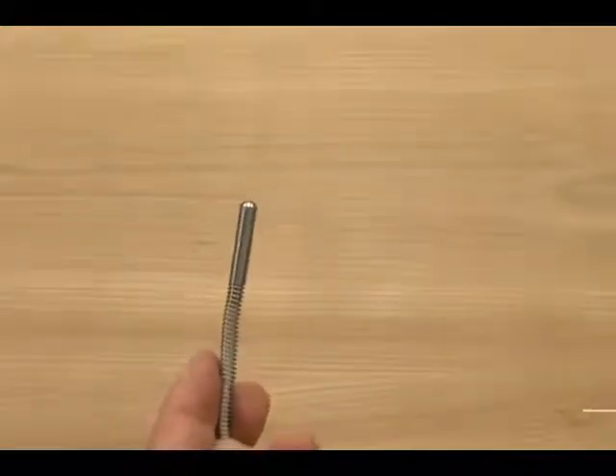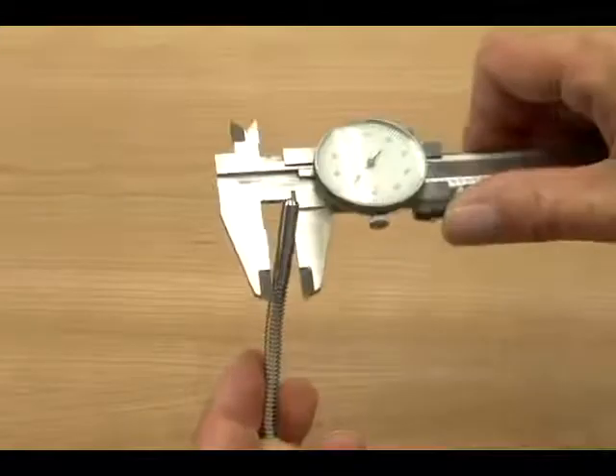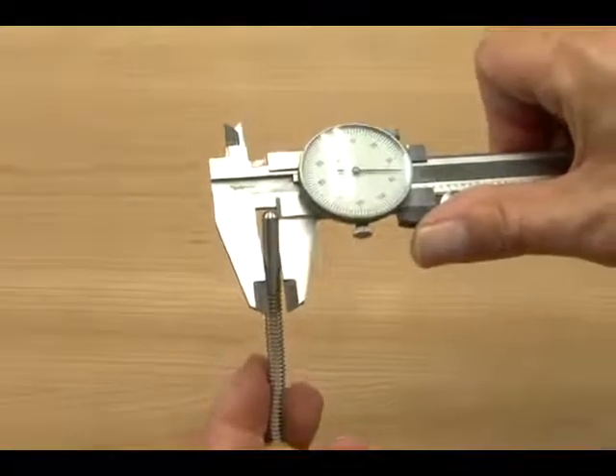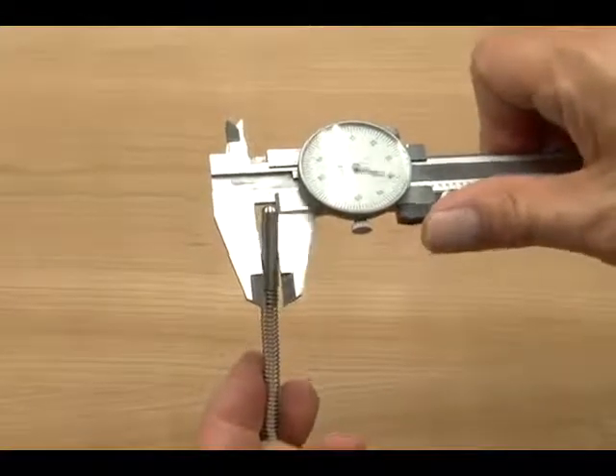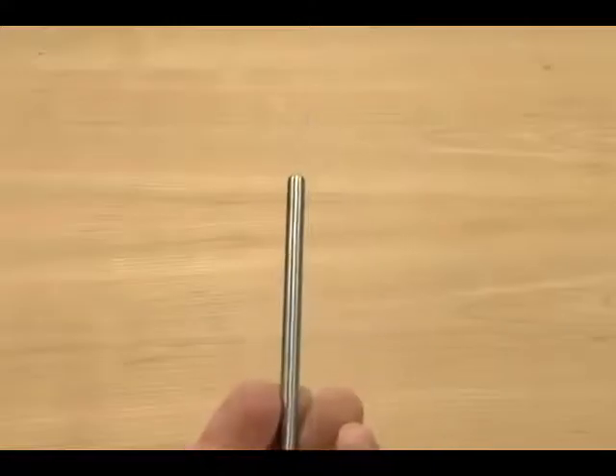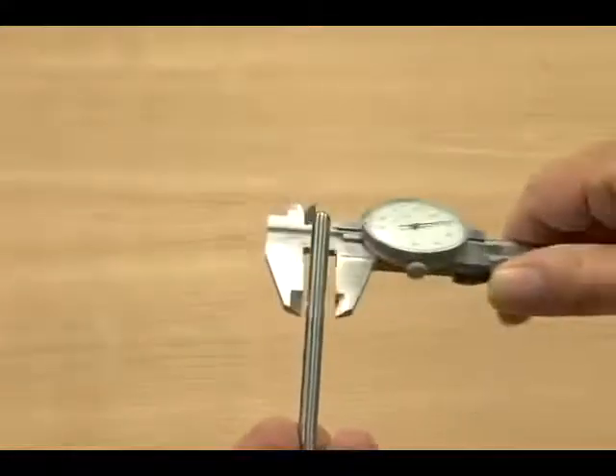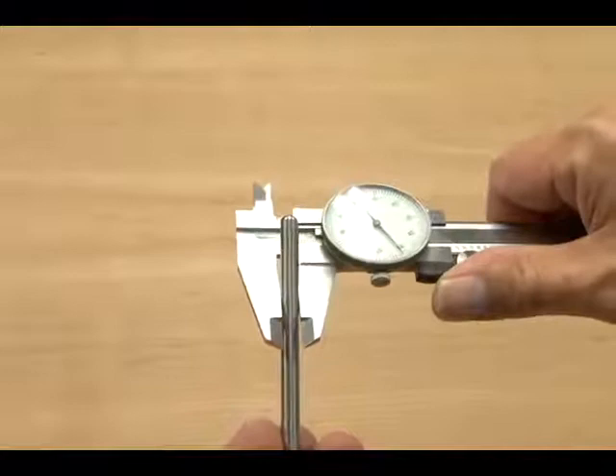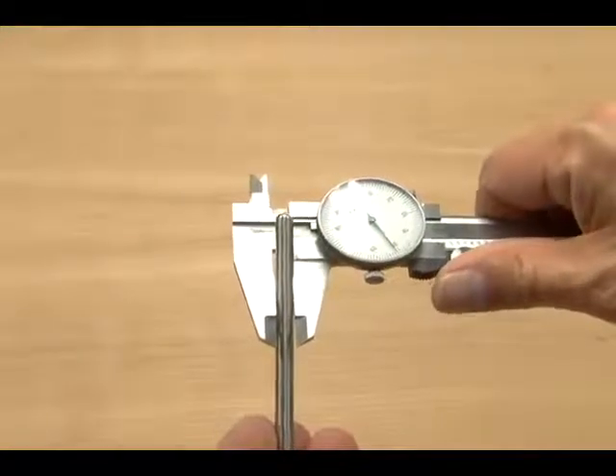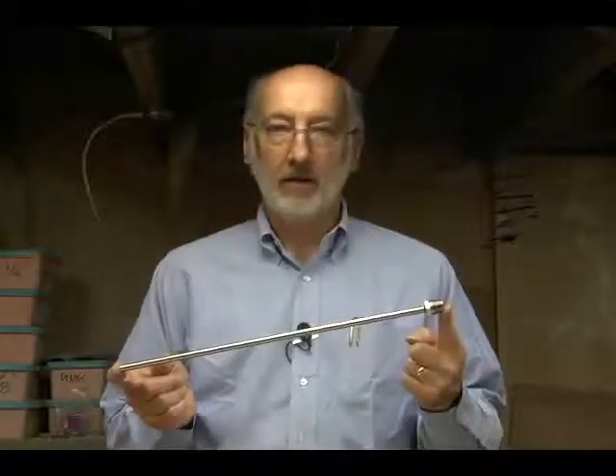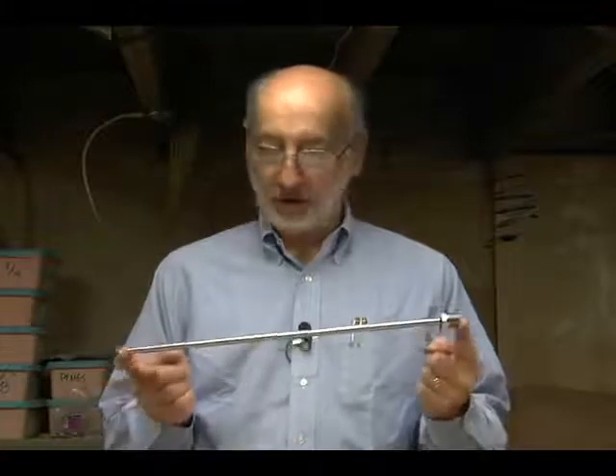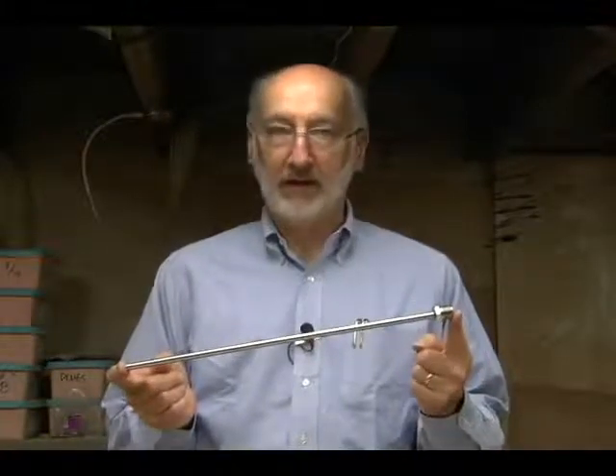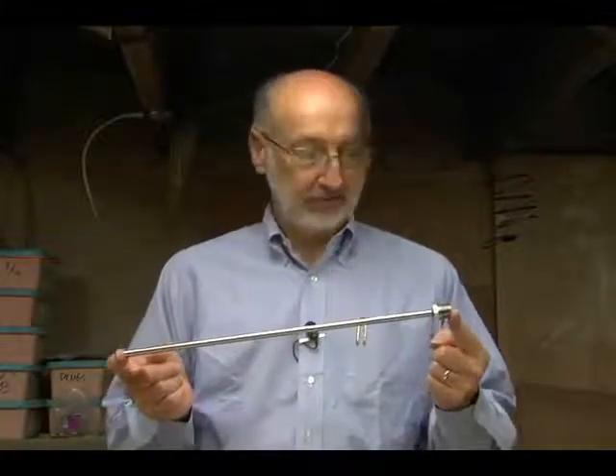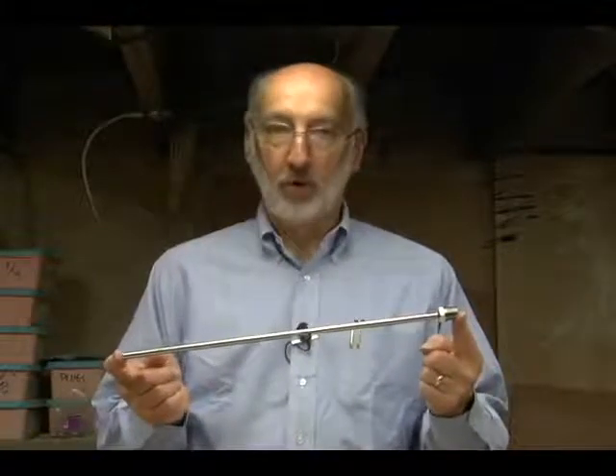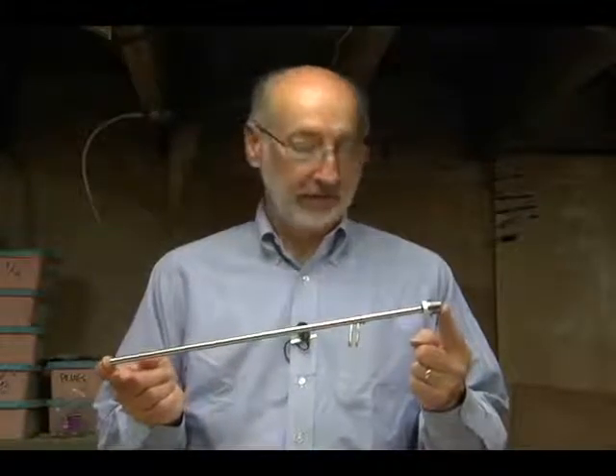If you have thermal wells that have suffered damage or corrosion, the worm will help you because it's only 237 thousandths of an inch in diameter. It's hard to see the difference, but this helps it slip into those tight thermal wells where a full 250 thousandths probe may be just a little too tight.